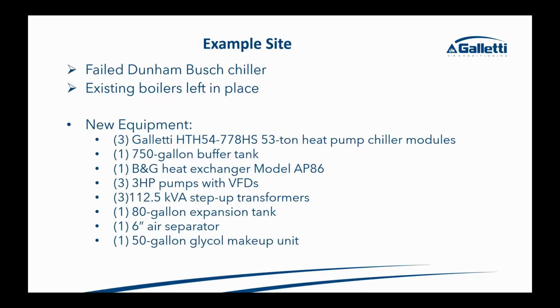So this property, they're currently conforming to next year's BERDO. The issue is that as of, I believe, 2030, they would be out of compliance. So it's not anything that they're concerned about now. But the thing is that they had a failed chiller. And they said, okay, well, if I replace that chiller, and it's pretty costly, then in X amount of years I'm potentially going to be paying a fine of X amount per day because I replaced that chiller with the same type I had there before.